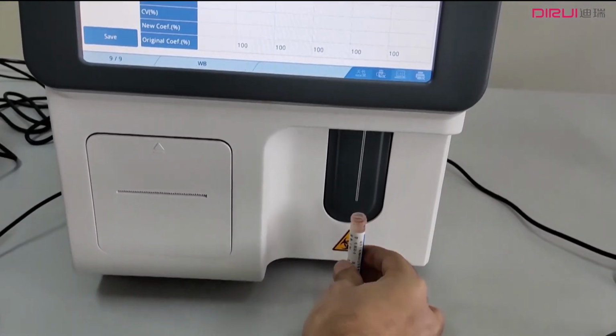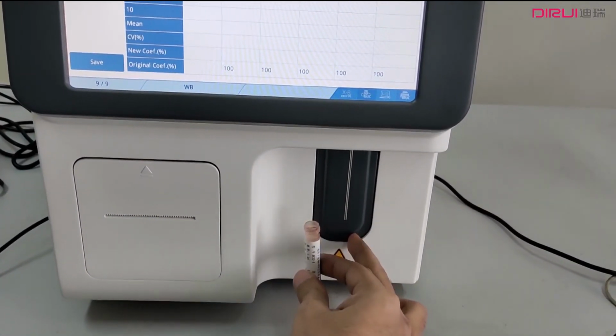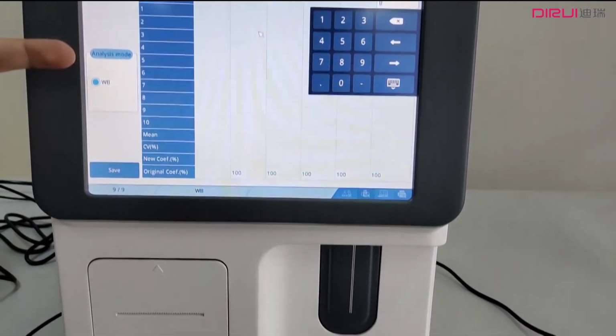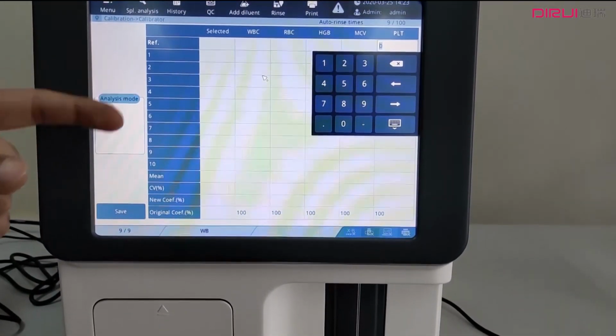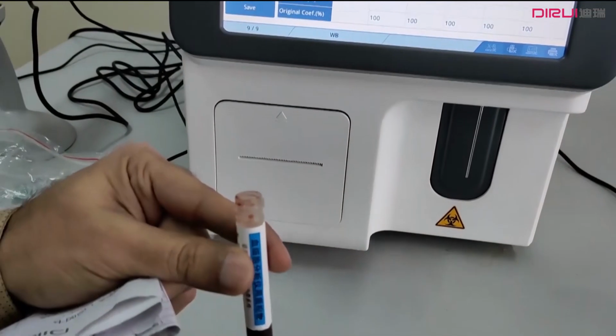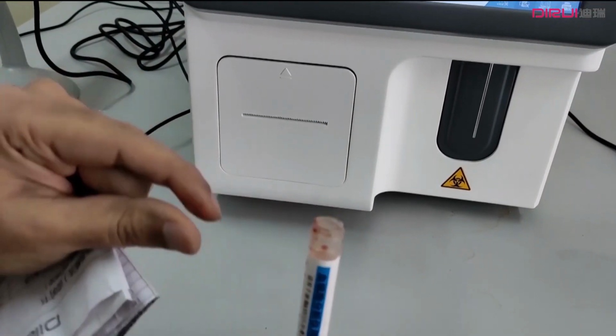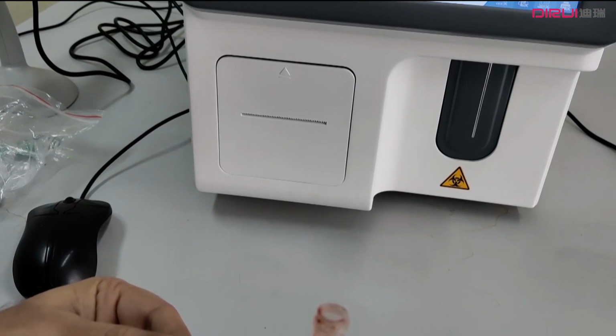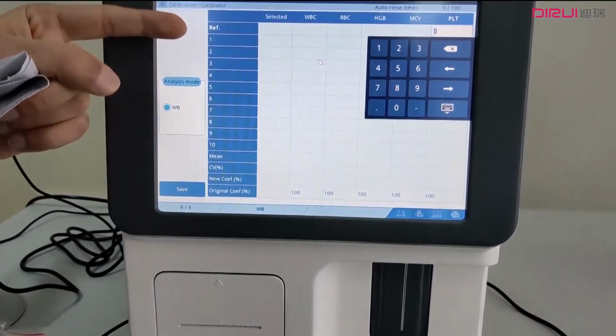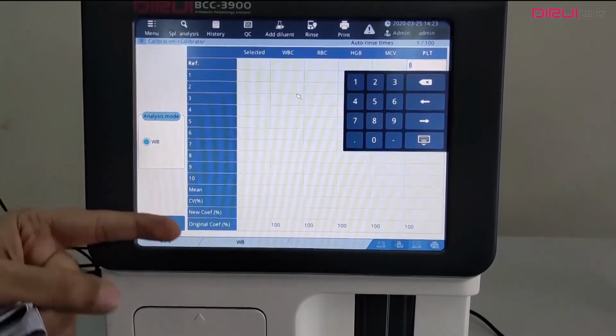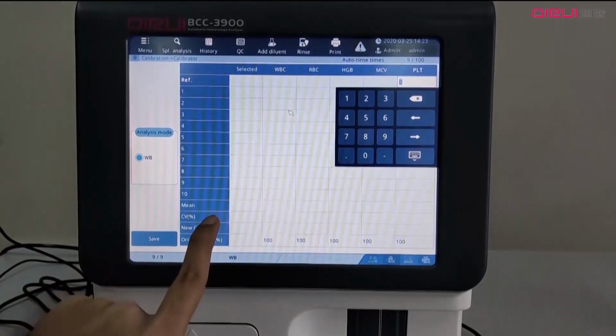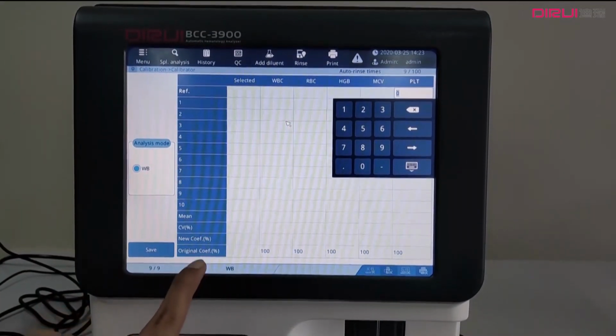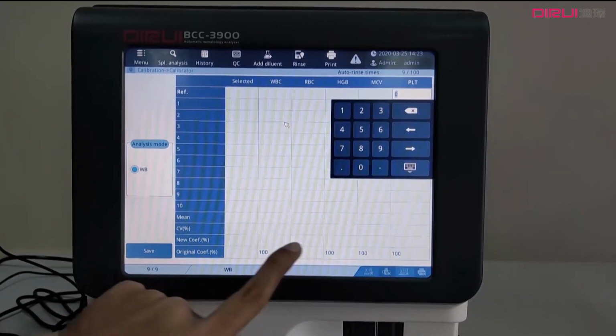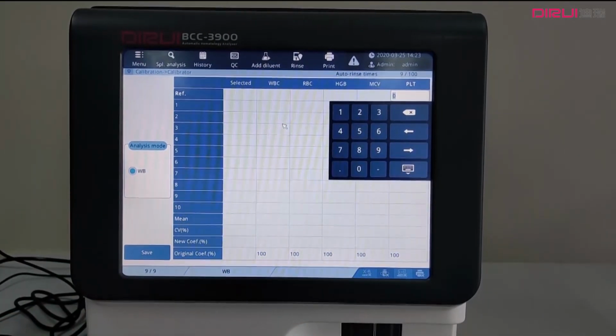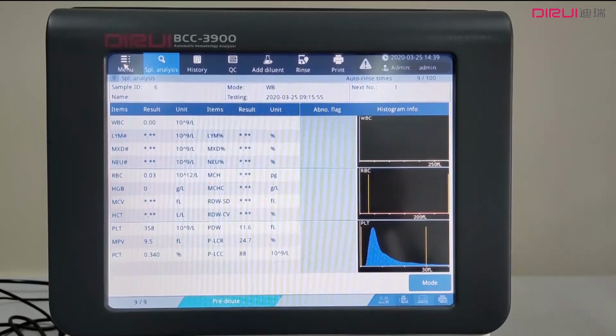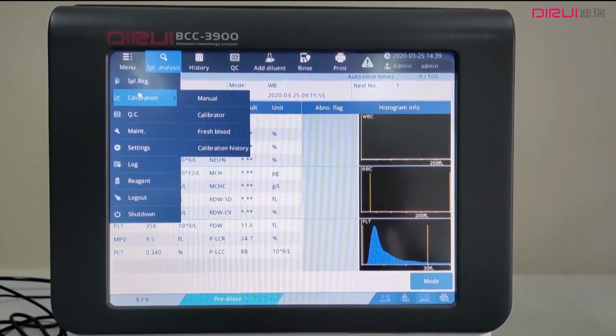Then put your calibrator under the probe and press this button. The recommended method is that after 2 or 3 tests, it is time to shake your calibrator again, 2 or 3 times, to get good results. Like this, do all of the 10 calibrations, and after all of the calibrations are done, the mean value, CV and all of the results will be shown here. Then press tab. Save.